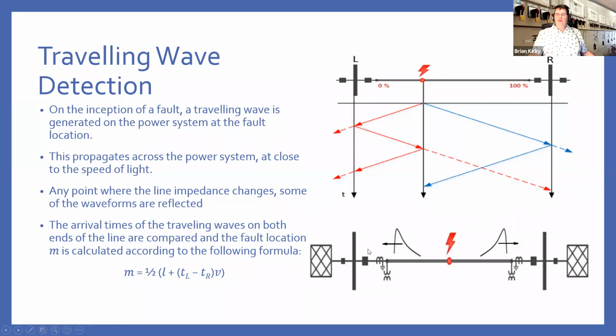On DC networks, it may also be very useful because faults tend to propagate at the same speed as the traveling wave. You may want to actually have some sort of high-speed detector which will instantly lock your line on this detection, because even things like the 3 millisecond delay on your protection may not be quick enough. You may be able to get faster using this, but this is something that has not been widely deployed on DC systems up to now.